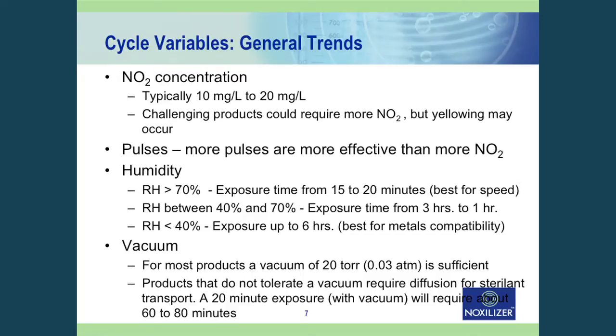Considerations when designing a product for nitrogen dioxide sterilization are no different than for ethylene oxide or hydrogen peroxide sterilization. The key variables in the process are NO2 concentration, the number of pulses (four pulses as shown in the graph), relative humidity — with a range of values that can be used — and also the vacuum. We go down to 20 torr in the vacuum, which is more of an efficiency value than a critical one. If you have a load with a lot of lumens and tubing, you might need a deeper vacuum so the gas can penetrate more efficiently, making 20 torr a typical value.